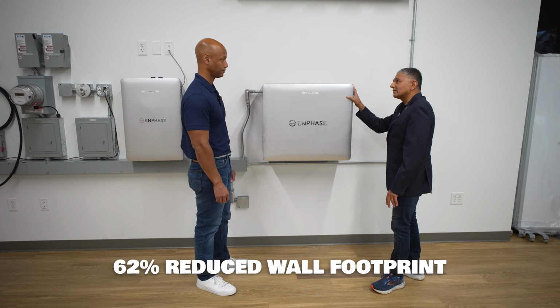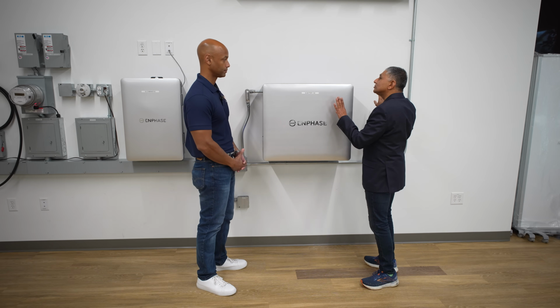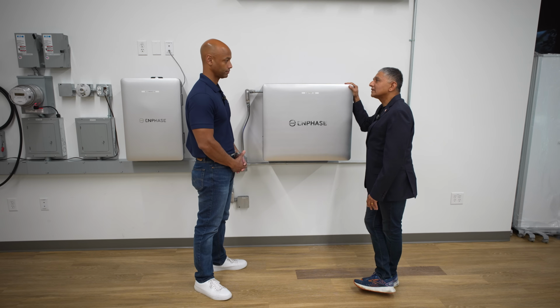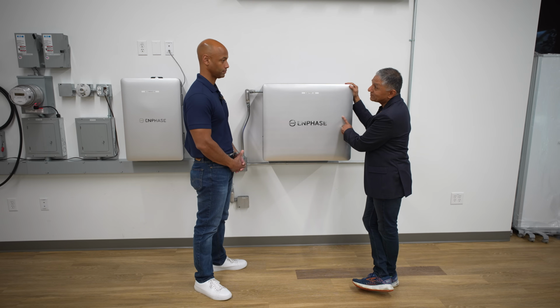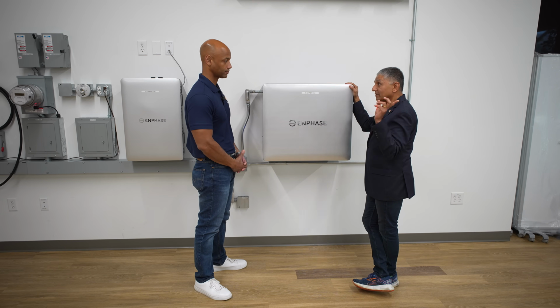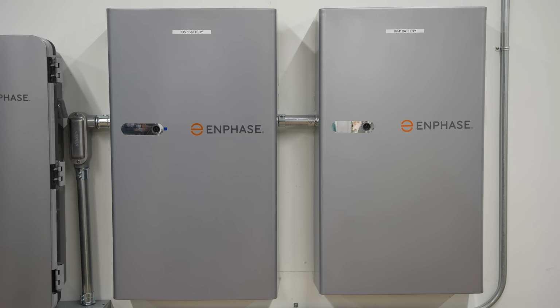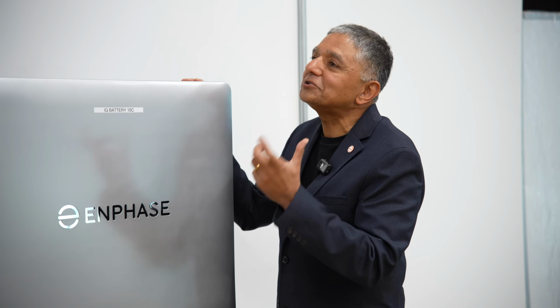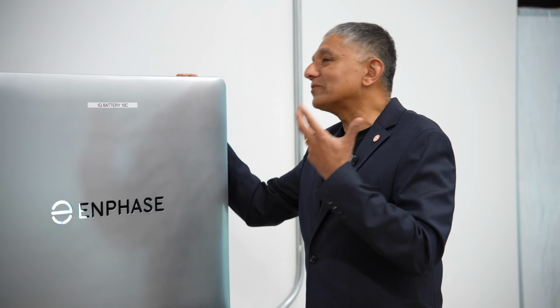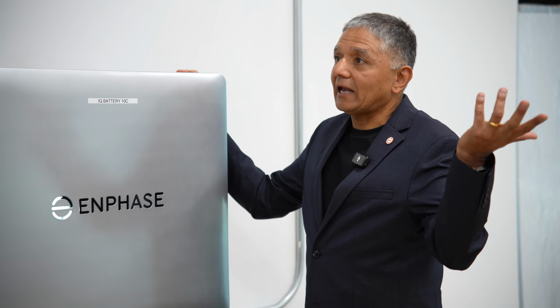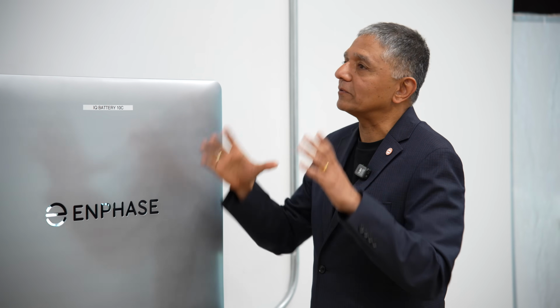The last thing we did has an impact on the balance of system: now it synthesizes neutral. In the older, 3rd generation system with the 5P, the balance of system had to synthesize a neutral because everything was 240 volts. So if you wanted to run a 120 volt load, which you typically do when running off-grid, we needed to synthesize a neutral using a neutral-forming transformer, which is a big hunk of copper and iron. That was in the old system controller, which is why it was so big. That went away now.